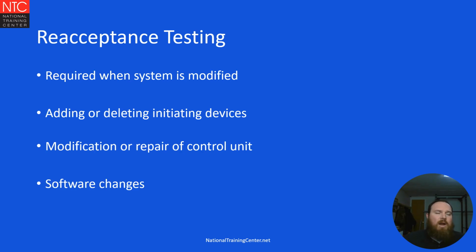If we are ever making any changes or modifications to the fire alarm system, we will have to do reacceptance testing. And as I had mentioned, it is required when a system is modified: adding any devices to the system, removing devices from the system. If we're making modifications or repair of the control unit, you're going to have to do reacceptance testing.